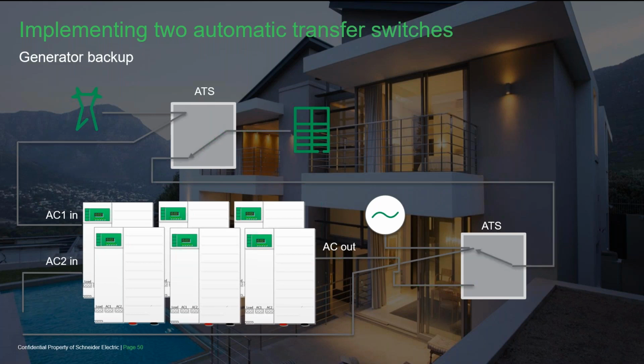When a low battery condition occurs, the generator is started. Make sure the ATS for the generator can have a delay in case the generator needs to warm up before picking up a load. The generator will run until the batteries are charged to the desired level, which is programmable. Then the generator will be stopped. The system will continue to operate like this until the grid returns. Many customers choose to only partially charge the batteries with the generator. That way the PV has a chance to get the batteries charged fully.